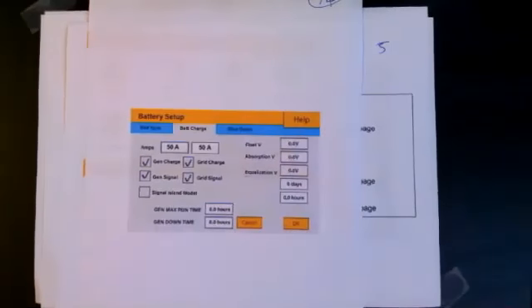Now, there are lots of batteries turning up. I'm seeing lots of little battery manufacturers turning up, and their communications are not very good, or they're not compatible with a lot of inverters. It's important, because it's really, really important for batteries to communicate. But if the battery is not communicating, it doesn't matter as long as those settings are correct, and you must get that out of the battery. If you have a wrong setting and you try to overcharge the battery, that's where you get a fire. You've got a fire risk, so you need to make sure they're correct. Otherwise, the thing will go on fire.